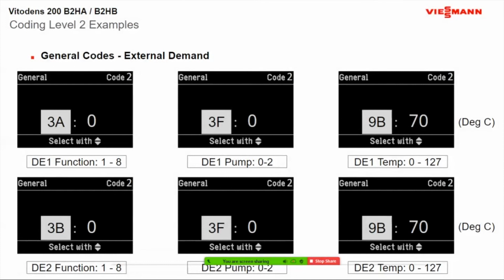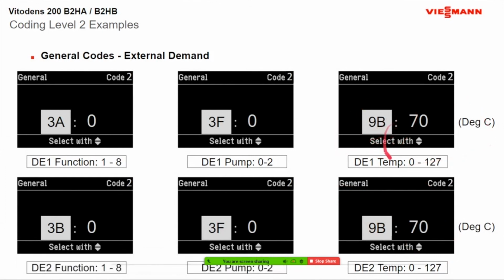If you were doing external demands the older way with HC1, HC2, and HC3 on DE1, DE2, unlike the zone circuits, these are heating circuits, you actually had to go into coding and make the changes to tell it what you wanted to do, and then what the temperature would be. 9B is your temperature change. So with the heating circuits, you could only have one fixed temperature, and that was by changing 9B. So if you had three different HC1, HC2, HC3, they're still following that same temperature output here.